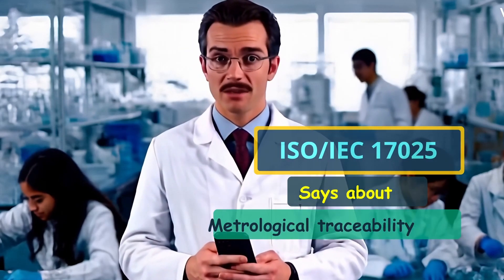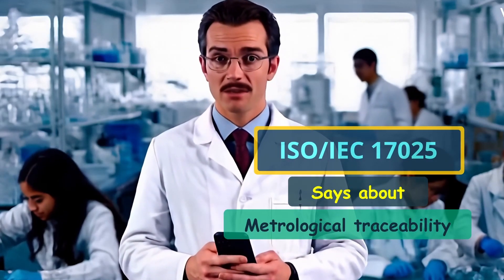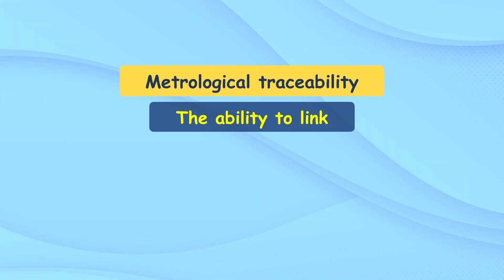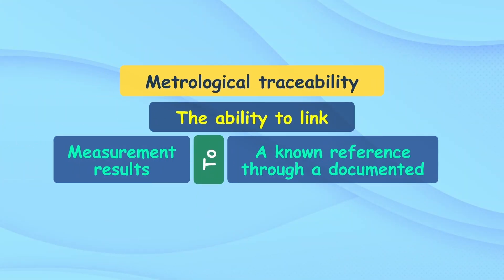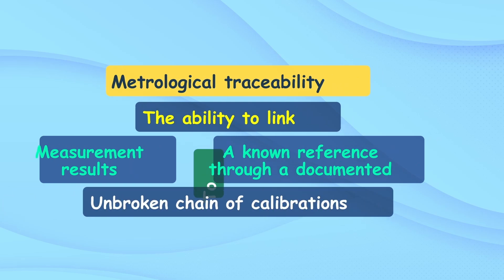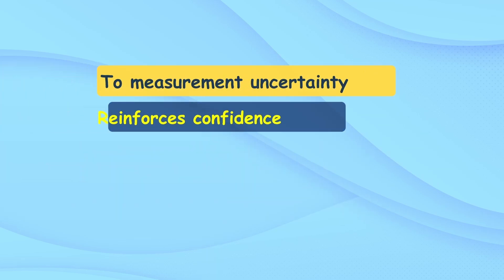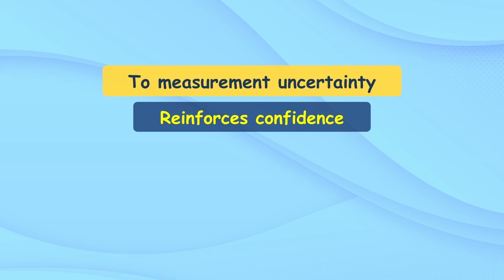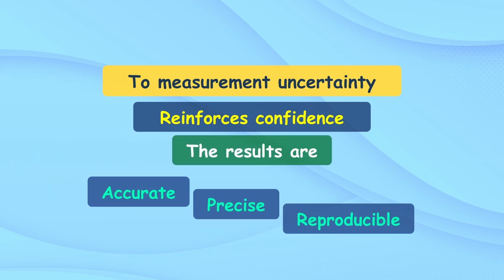Now that you know the traceability pyramid, it is time to understand what ISO/IEC 17025 says about metrological traceability. Metrological traceability refers to the ability to link measurement results to a known reference through a documented, unbroken chain of calibrations. Each step in this chain contributes to measurement uncertainty but also reinforces confidence that the results are accurate, precise, and reproducible.